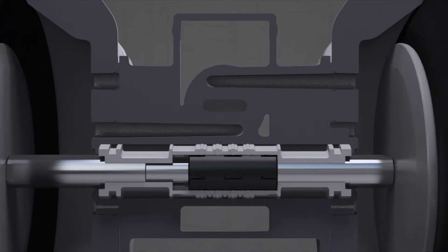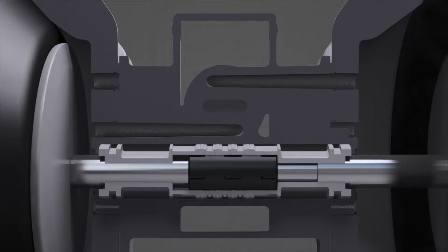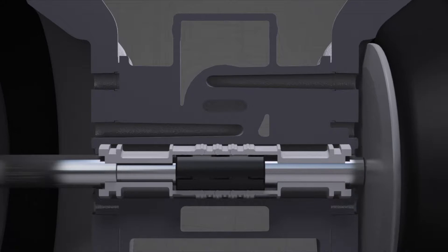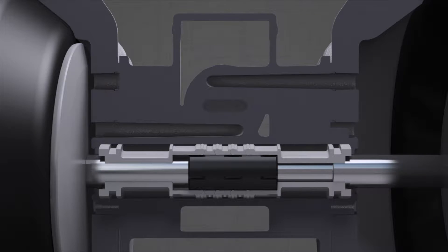The pilot and main air valves work together to drive the pump. The pilot air valve has two logical states, which we will call left and right. Pressurized air enters chamber three in the middle of the pilot valve sleeve. Chamber three is always under pressure.